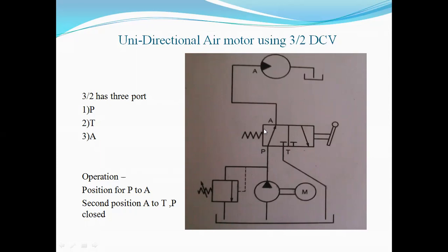Okay. Now, if you change the direction control to a 4x2 direction control, what will happen? There is no outlet provided for the return line. So forcefully, if we connect the 4x2 direction control in this case, where the actuator is a unidirectional actuator, then as per the construction of your motor or your pump, when it is unidirectional, it is not allowed to rotate in the opposite direction in any case.